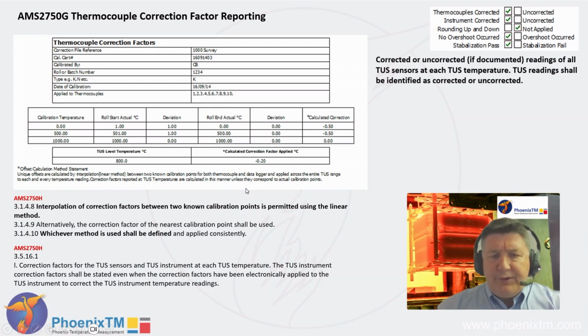To give full certification to the thermocouple correction factors in the TUS report that the Thermal View survey generates, we give all of the information created within the correction factor file. And as you can see here, as I've said before, the calibration for this particular thermocouple was done at 0, 500 and 1000. The TUS temperature was actually at 800 degrees, but using the linear interpolation method, we were able to calculate the corresponding correction factor at 800 from the calibration data itself. So we satisfy everything we need within the AMS 2750 specification and also CQI-9.